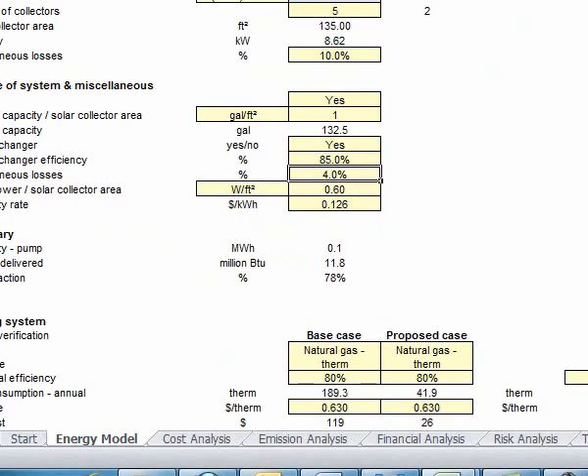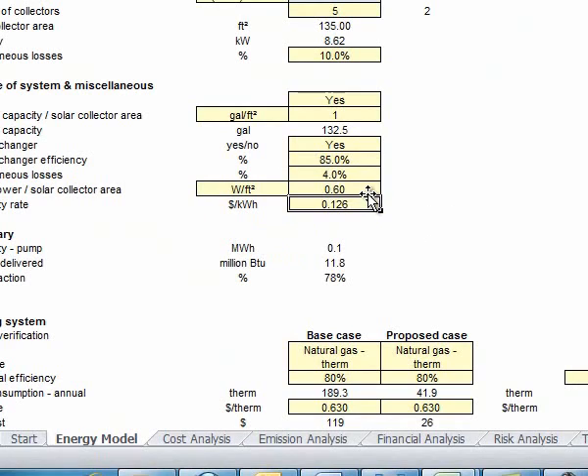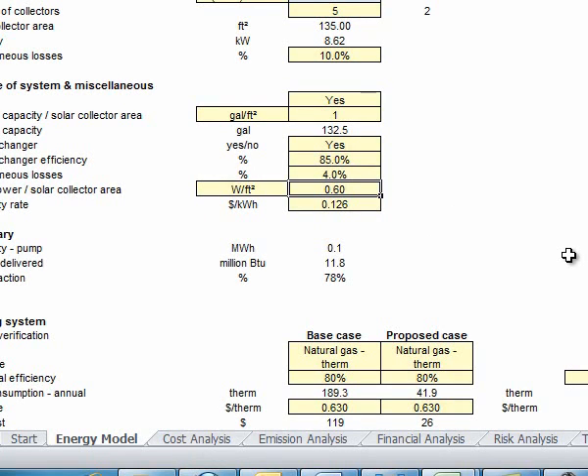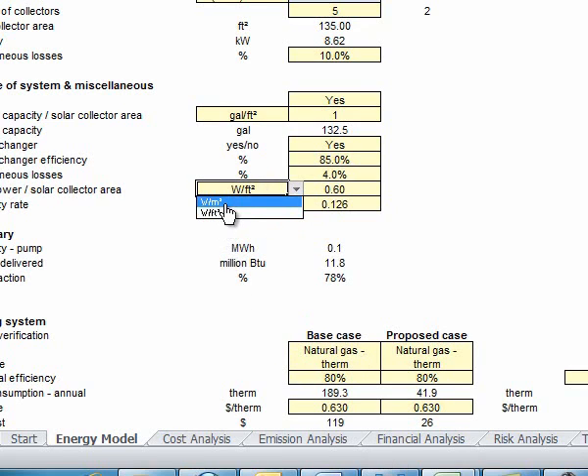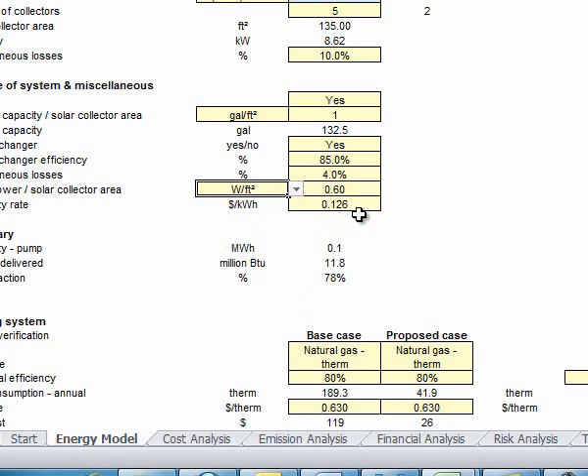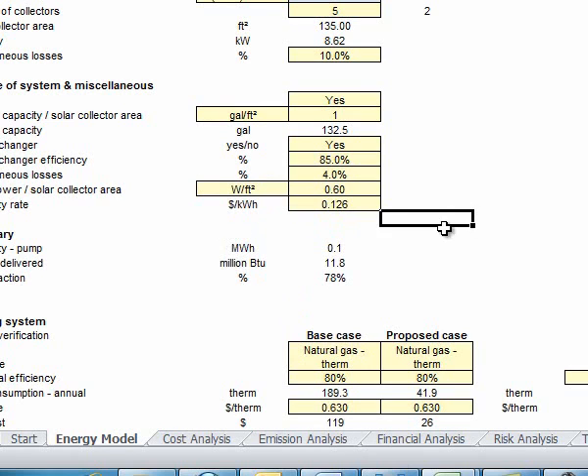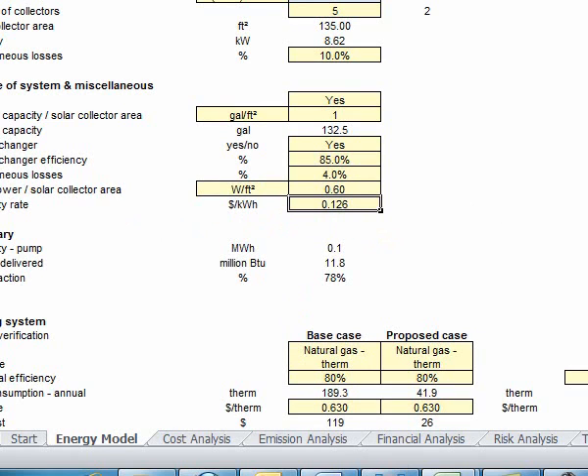Data that we've gleaned from the internet and from Ross at the MREA has kind of given me the impression that I'd like to keep my pump power, the power it requires to run that electrical pump to pump the fluid from the storage tank to the collectors, is about 0.6 watts per foot squared. Now, I got beat on a few times because I had the thing at watts per meter square, so make sure it's per foot square. And then at my electrical rates, I again went conservative as 0.126, so 12.6 cents per kilowatt hour is the electrical rate.